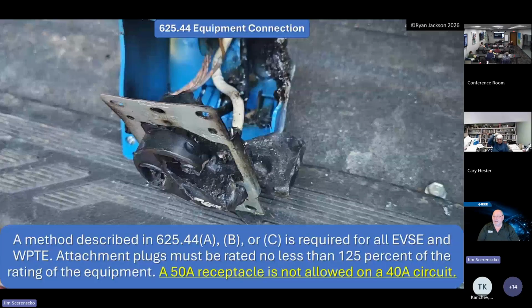The other problem that's been happening is this. These 50 amp receptacles have never been designed to have something plugged into them under continuous use for like 10 or 12 hours. And so all these plugs have been melting out of the walls, and the boxes themselves have been melting and starting fires. So now 625 requires that all EVSE and WPTE attachment plugs be rated not less than 125% of the rating of the equipment. A 50 amp receptacle is not allowed on a 40 amp circuit.